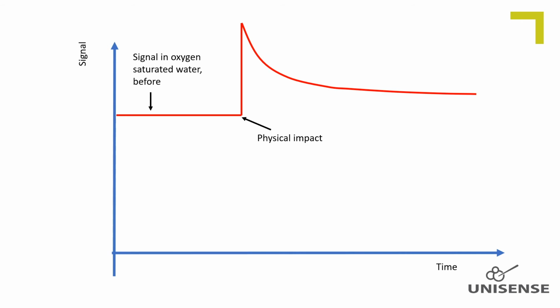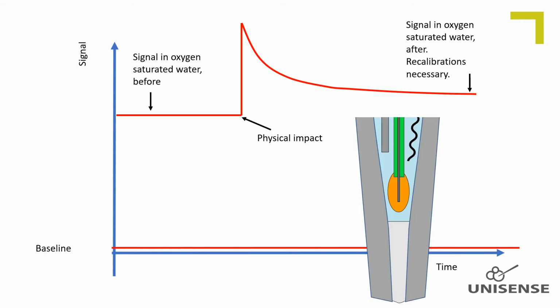Physical impact on the sensor can, besides destroying the sensor, change the sensitivity and thereby the calibration of an oxygen microsensor. The working electrode connects to the amperemeter via a thin, flexible glass covered platinum wire. Physical impact, which shocks the internal components, can induce a displacement of the working electrode position relative to the membrane, and thereby change the sensitivity. Typically, such impact will induce a sudden signal peak followed by a stabilization time, but the sensitivity might not return to the original sensitivity due to a displacement of the working electrode position.